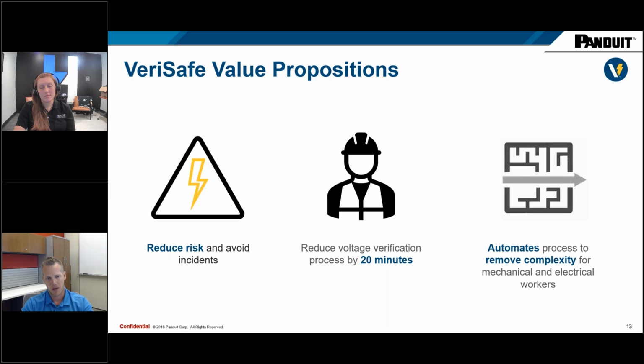When you think about these different panels, no 2 panels are created the same. I'll say that with a little caveat that there are redundant systems, a lot of similar panels, but they're all labeled differently. MCC buckets, higher or lower, hot environments, all that stuff increases complexity and creates hazards or potential for hazards. VeriSafe automates all that, so you don't have any of that. It's pushing the button the same way every time, and whether it's a high panel or a high bucket or a low bucket, you interact with it in the exact same way. So there's a lot of consistency there, which helps reduce complexity.